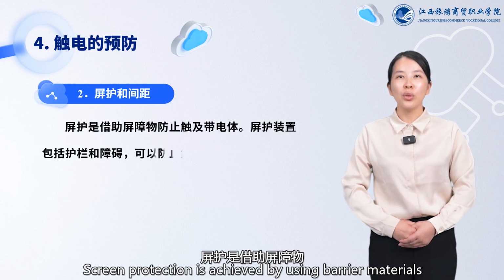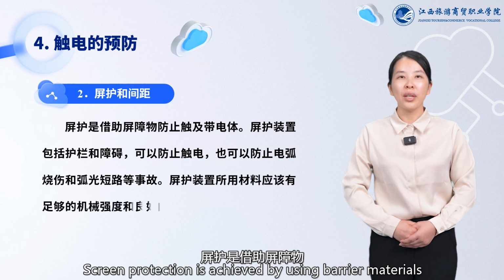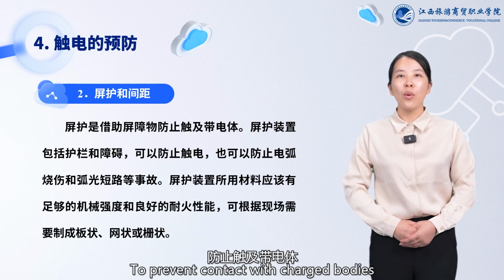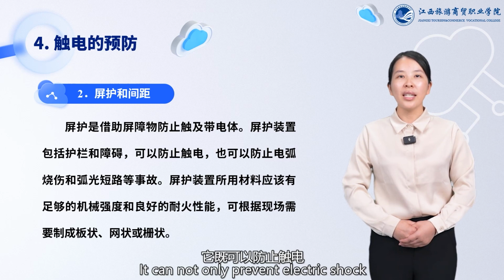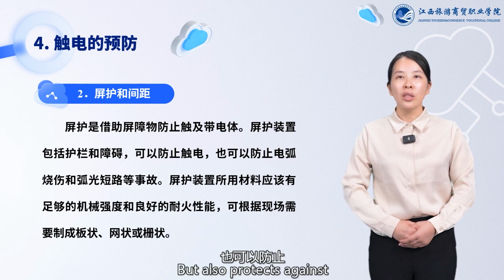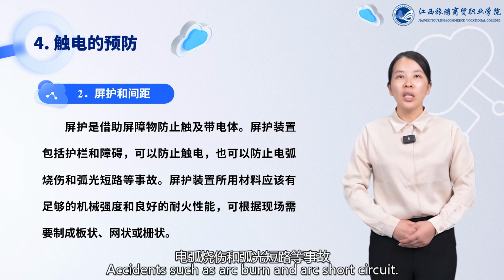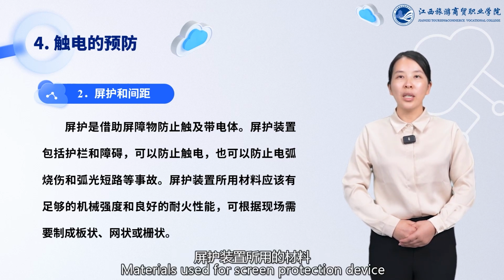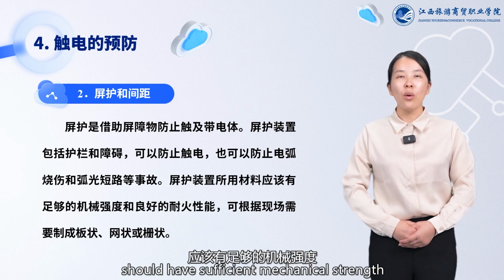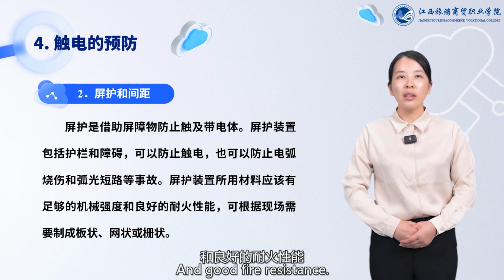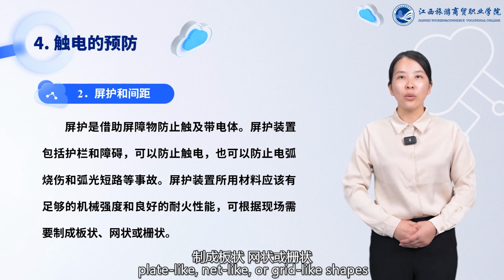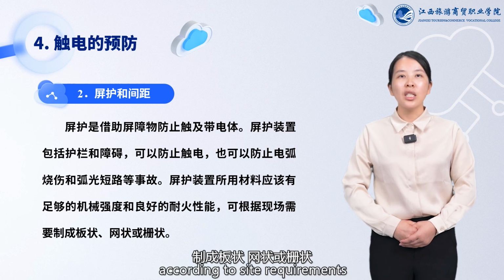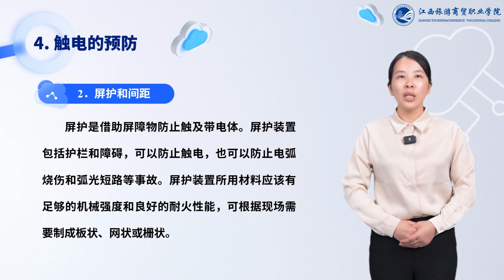Screen protection is achieved by using barrier materials to prevent contact with charged bodies. It can not only prevent electric shock, but also protects against accidents such as arc burn and arc short circuit. Materials used for screen protection device should have sufficient mechanical strength and good fire resistance. They can be made into plate-like, net-like, or grid-like shapes according to site requirements.